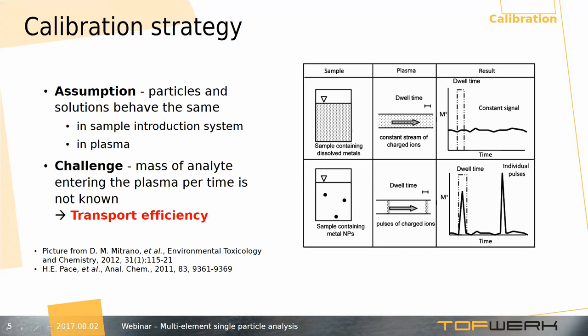Solution, in contrast, is introduced in the form of a continuous flow of ions, forming a continuous signal. If we assume that solution and particles behave in the same way in the sample introduction system and in plasma, and we know the mass flux of our solution — how much is being introduced within this dwell time and the corresponding signal — then from these figures of merit we can convert our signal intensity into element mass.